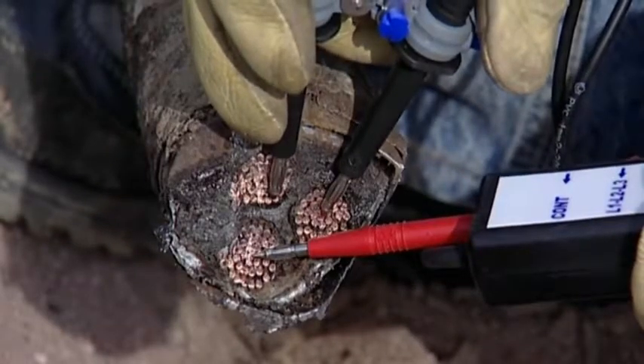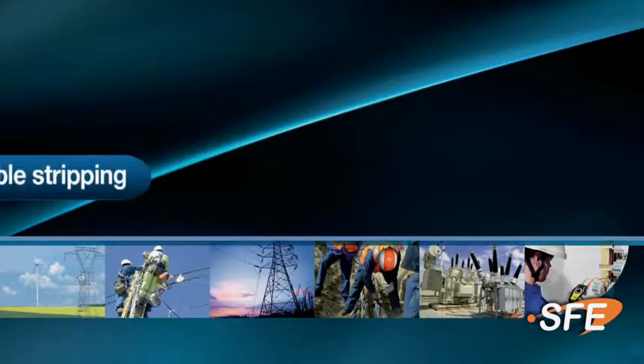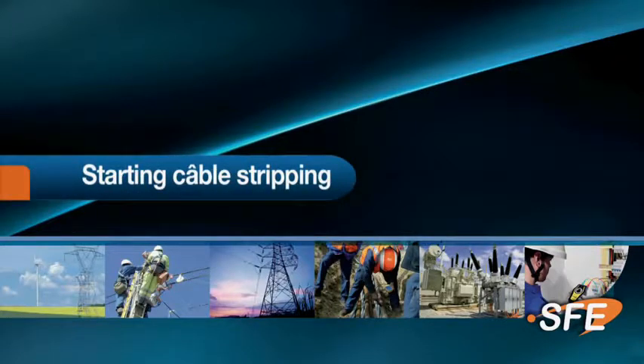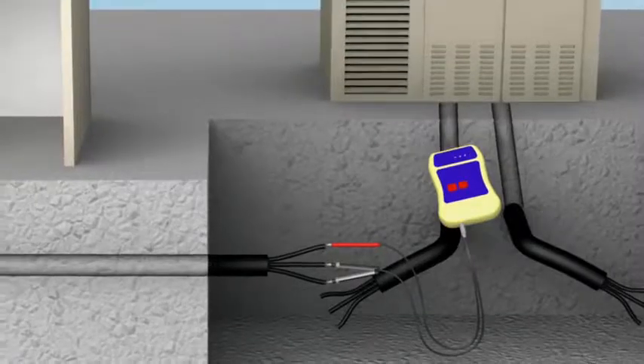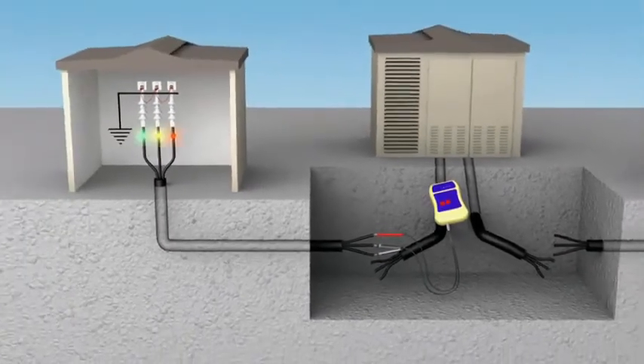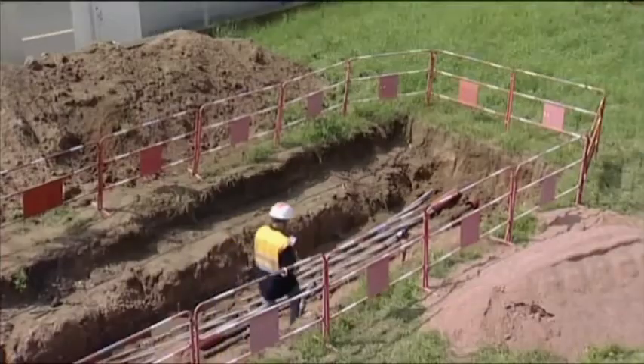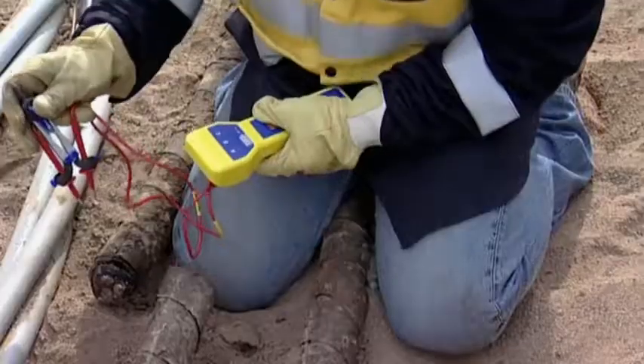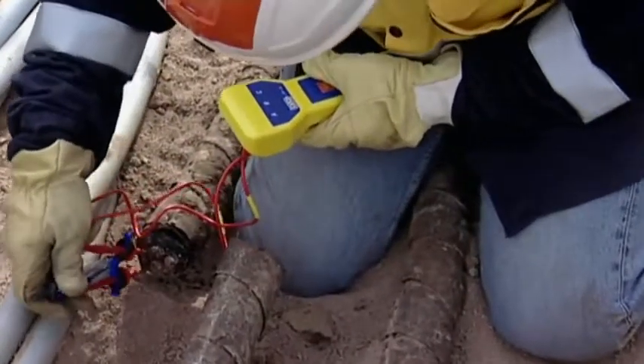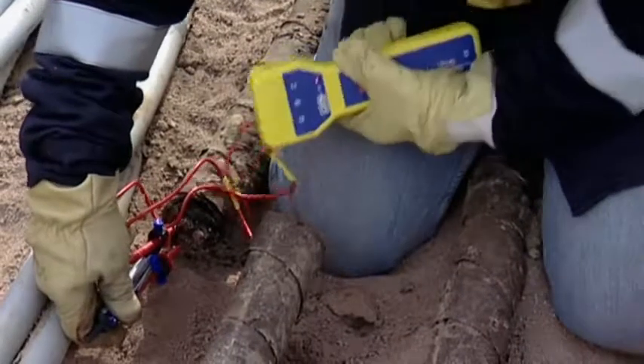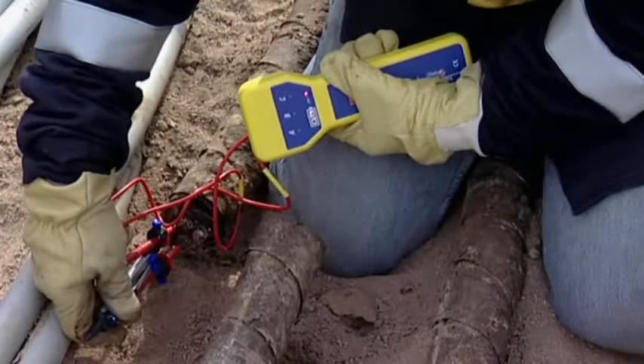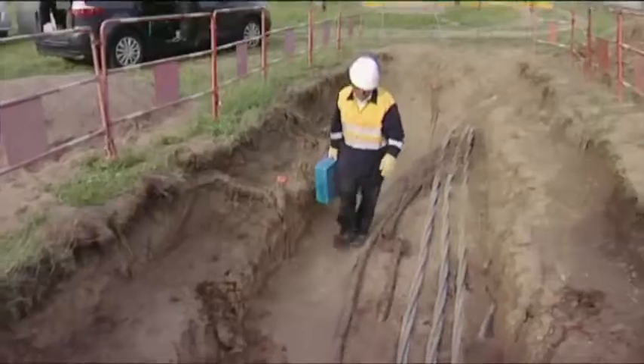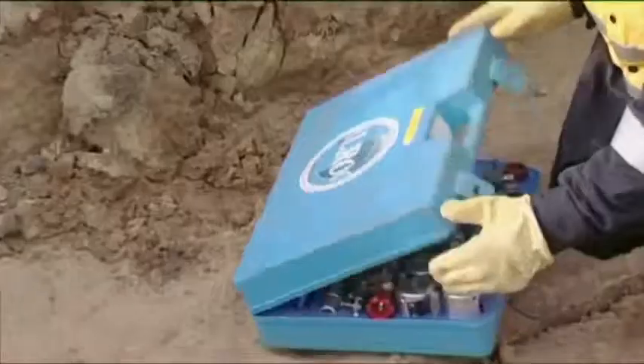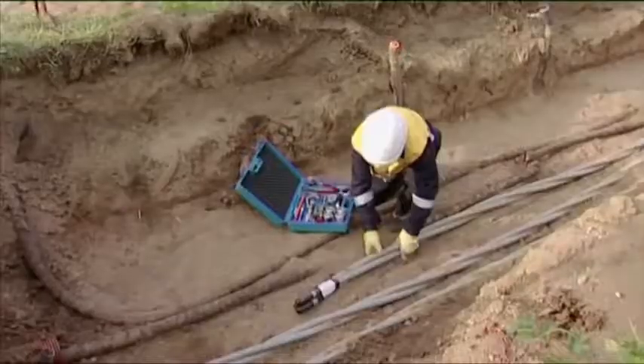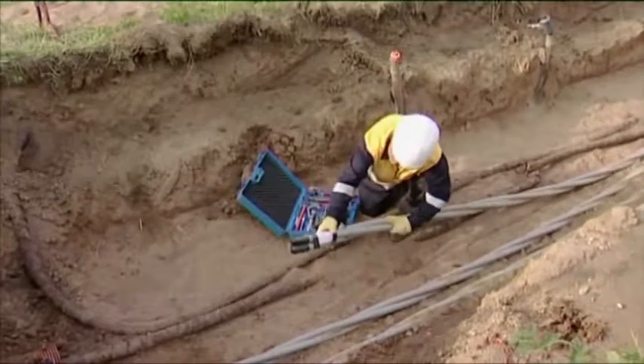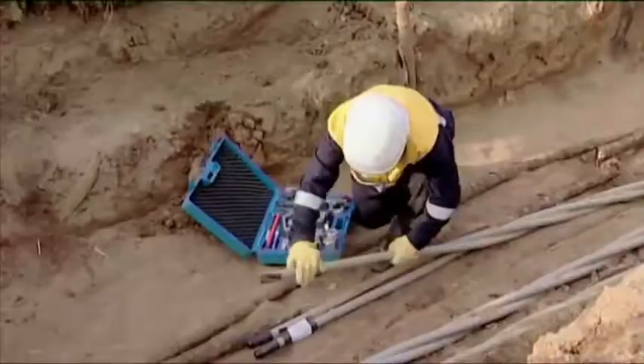FC2300 cable identification. Now that we're certain of being protected by proper grounding of both ends of the cable, we can start work. First, you must identify the phases, still using the FC2300 and FC2100. Then you prepare the cable end sections to set up the connections. You save time by applying the right professional methods using the right tools, so you don't have to come back in 6 months.